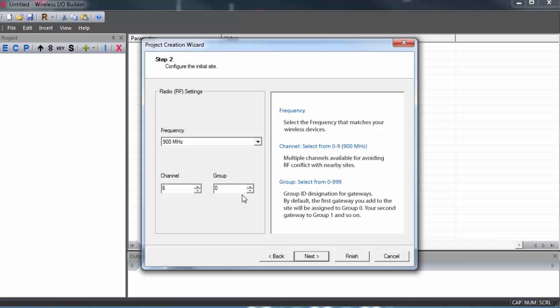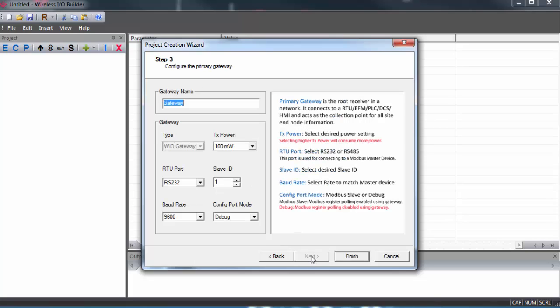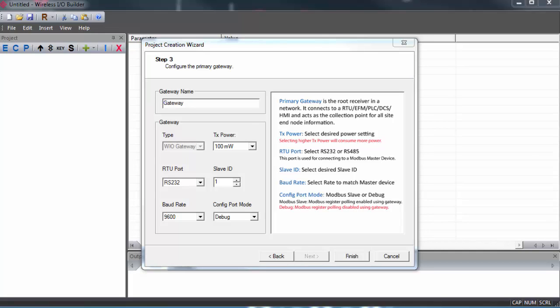Finally, we can set our group. In this instance, the term group is used to refer to individual multipoint wireless I.O. gateways and whatever I.O. modules they are connected to. By default, the first gateway you add will be assigned group zero, and the next gateway you add will be assigned to group one, and so on. All you need to know is that you can't have two gateways with the same group number on the same network.